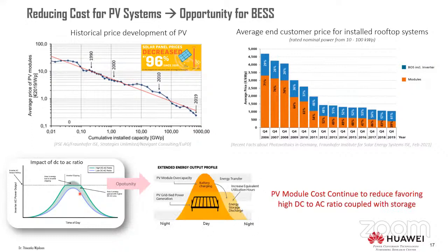On the other hand, there's another opportunity - if you integrate an energy storage element into the system, all the energy you are clipping, you have a chance to charge a battery, and then you can either feed it back to the grid when you have no energy produced by the PV, or do self-consumption. This is actually quite attractive. PV module costs continue to reduce, which favors a higher DC-AC ratio coupled with energy storage.